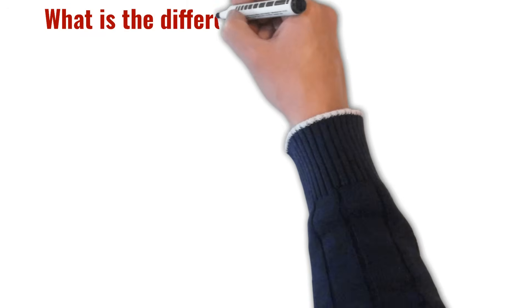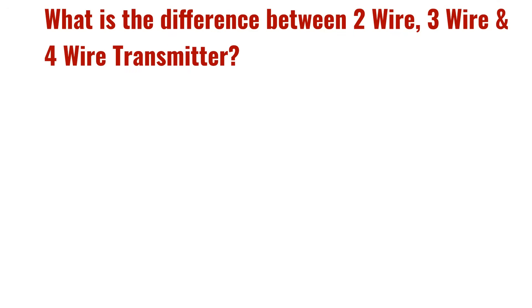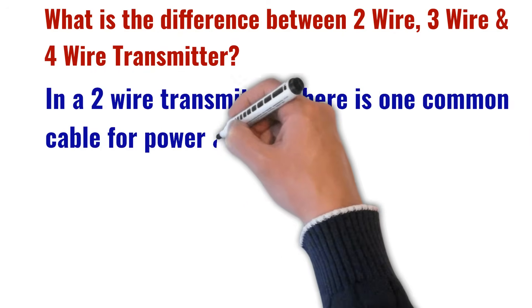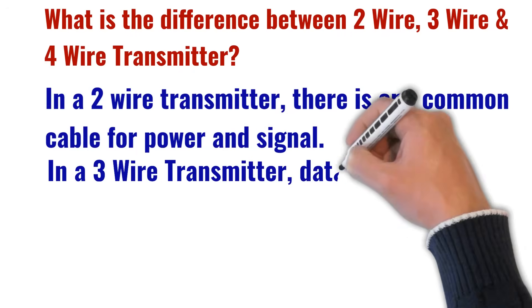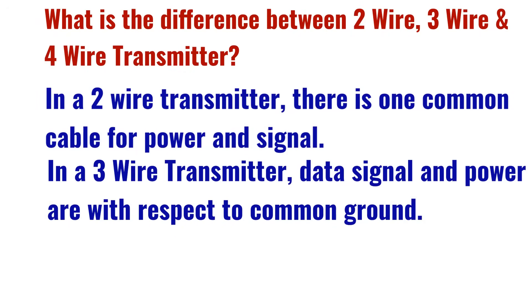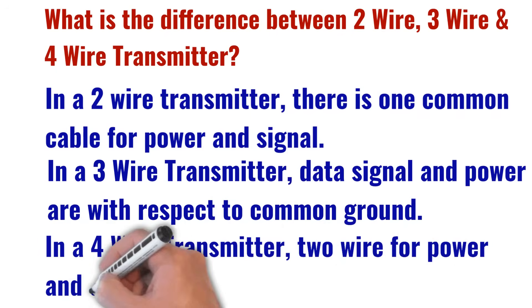The fifth most frequently asked interview question is: what is the difference between two-wire, three-wire, and four-wire transmitters? In a two-wire transmitter, there is one common cable for both power and signal. In a three-wire transmitter, data signal and power are with respect to a common ground. And in a four-wire transmitter, there are two separate wires for power and two separate wires for signals.